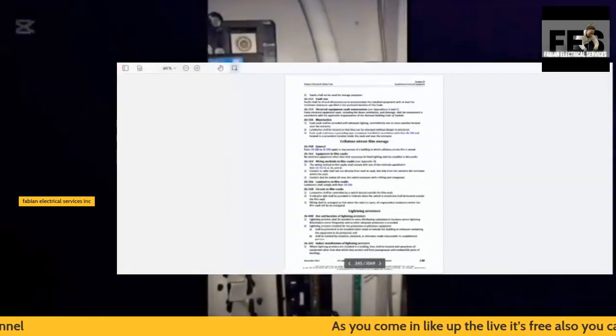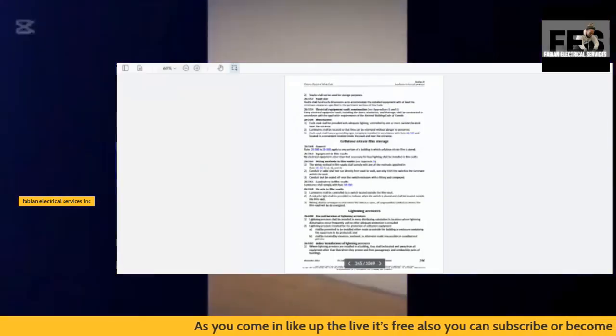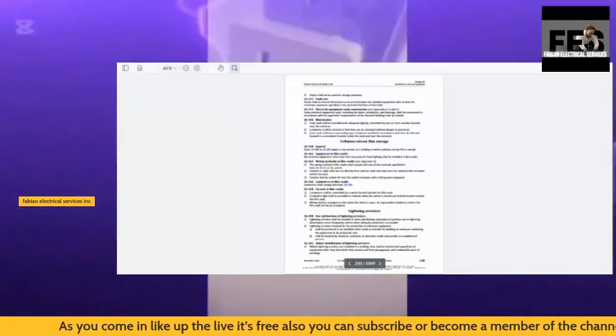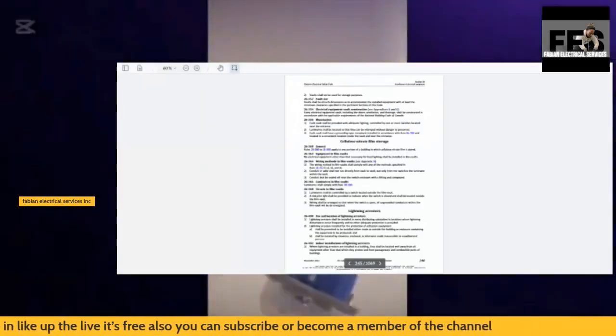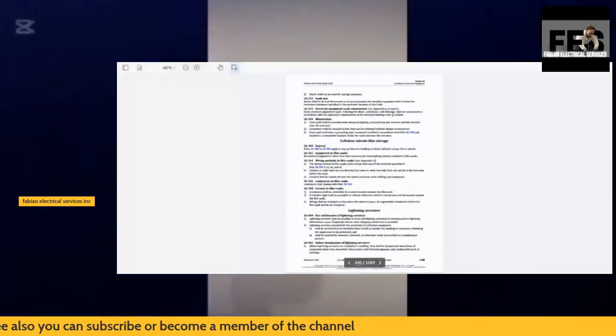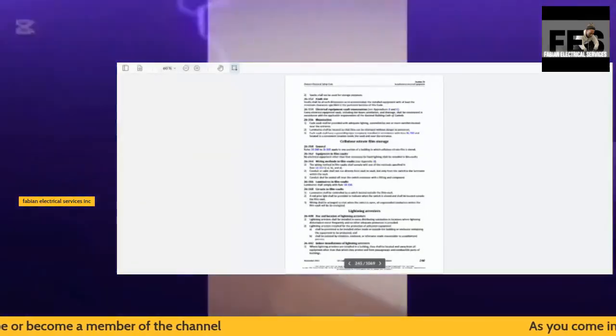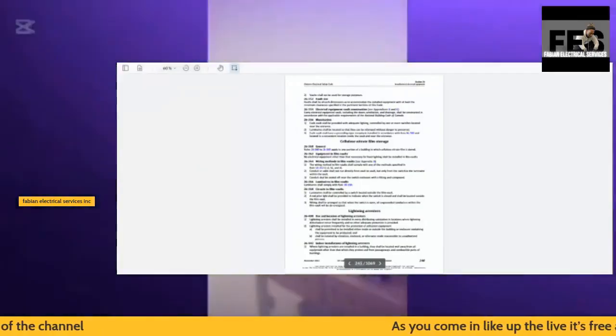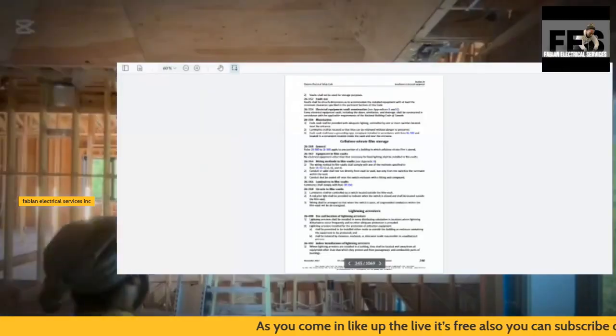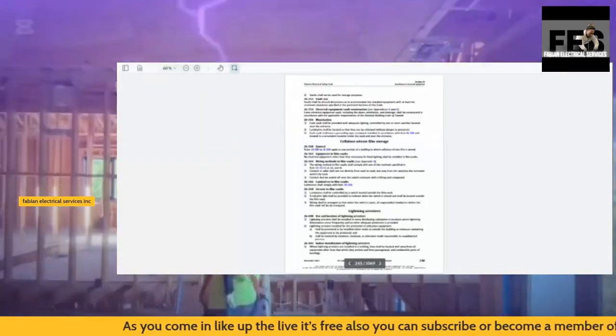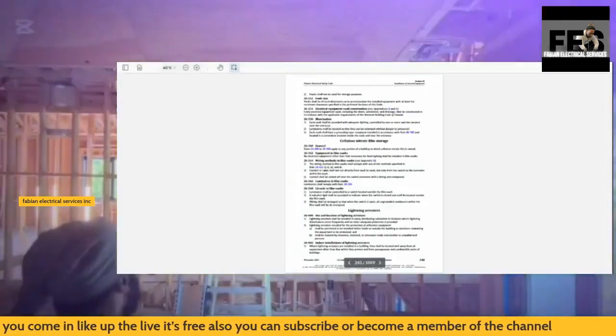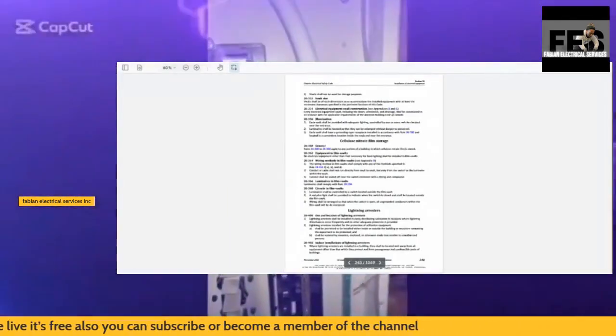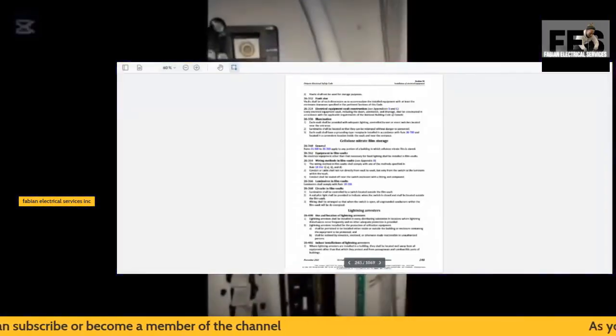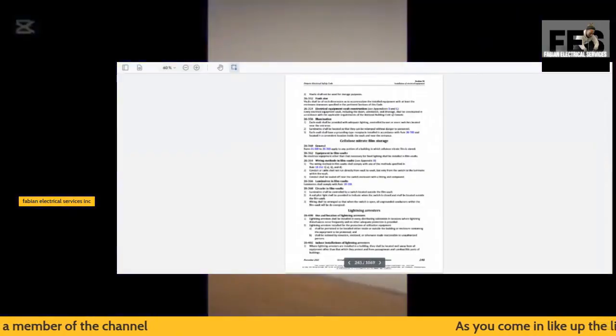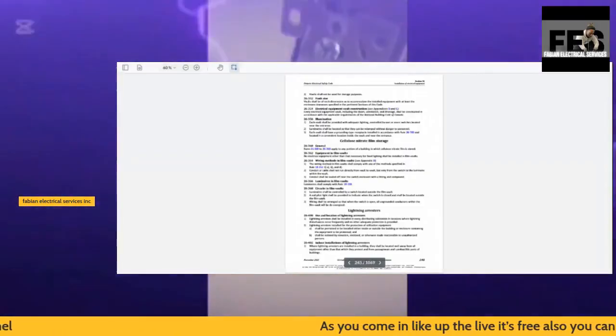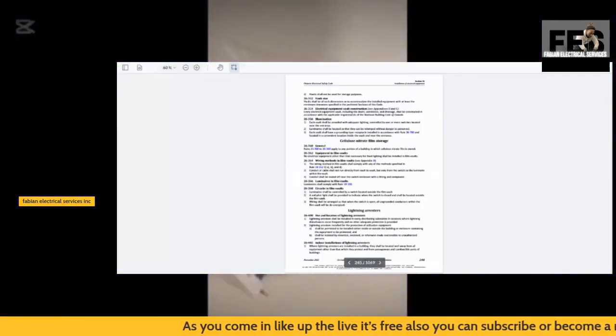So again, also wire connections. Hot wires should be connected to the appropriate lugs on the breaker, and the other end of the cable should be connected to the main panel. Also, safety: always disconnect power at the main breaker before working on any electrical components. And important notes, sub-panels do not add capacity to the overall electrical system. They simply distribute power to different areas.